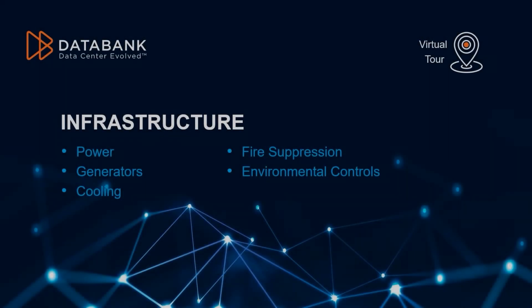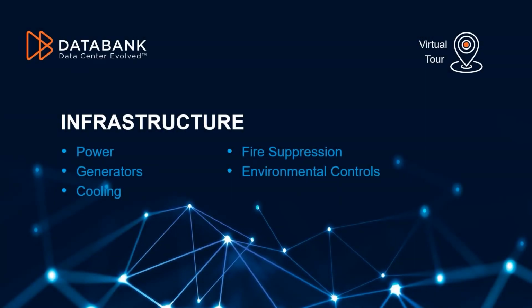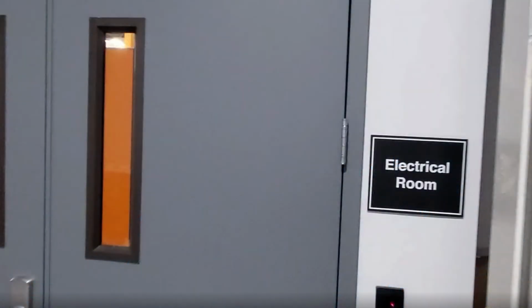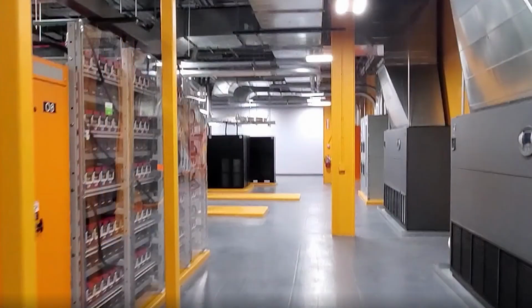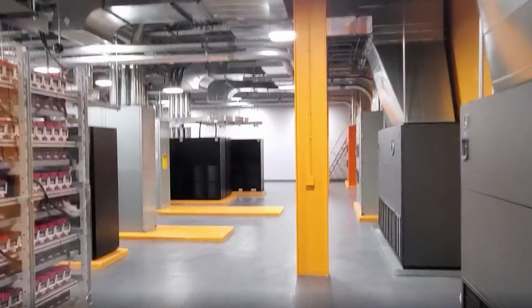Moving on to our infrastructure that supports your infrastructure, let's talk about power. For the ultimate in uptime, power is delivered in a 2N UPS configuration. All customer power has a primary A side and a secondary B side from the serving UPS all the way to your cabinet. The whips are also color-coded, which helps you quickly identify the difference. There are 6 total UPSs on site.